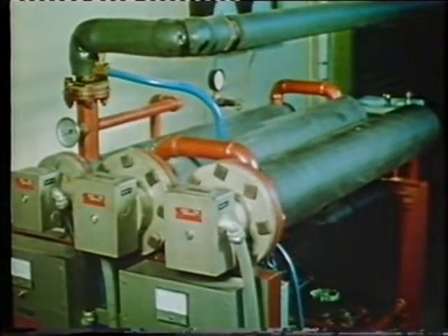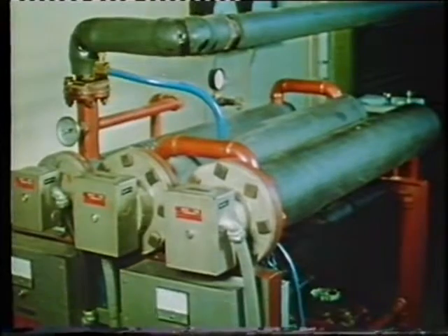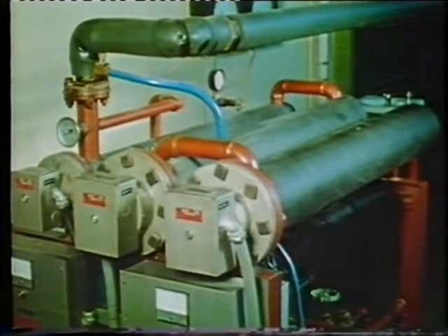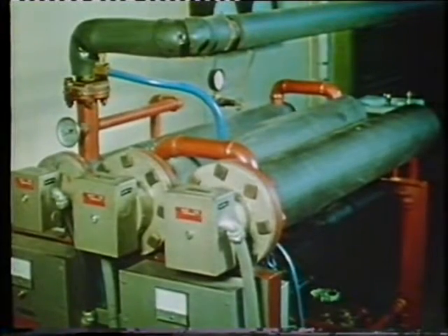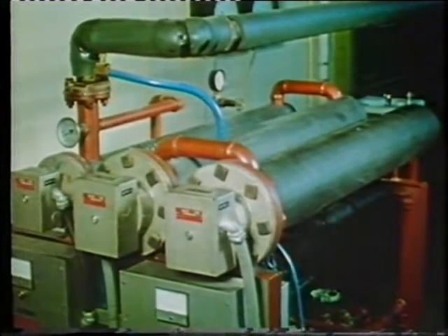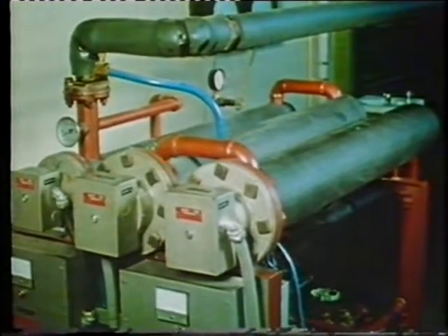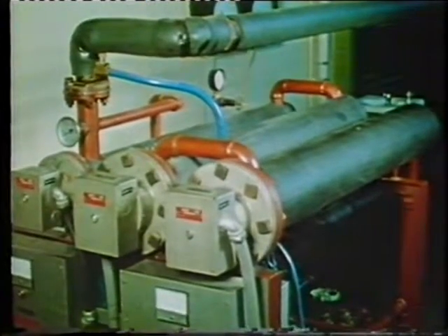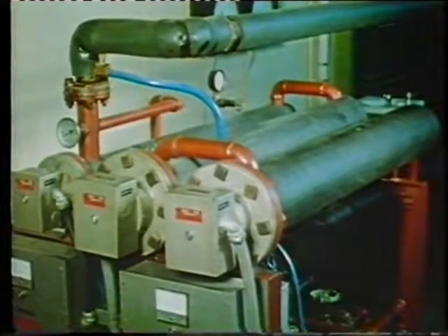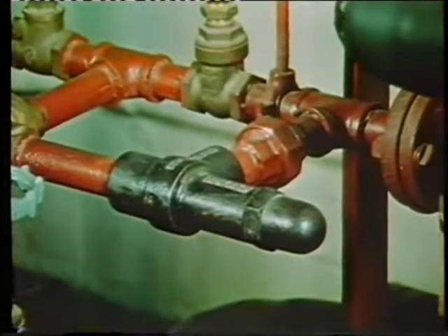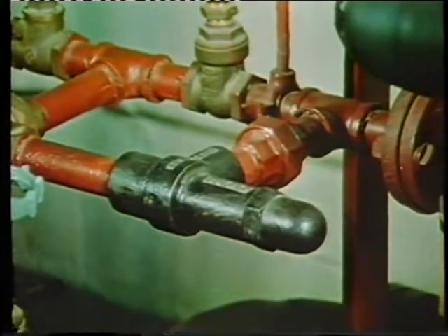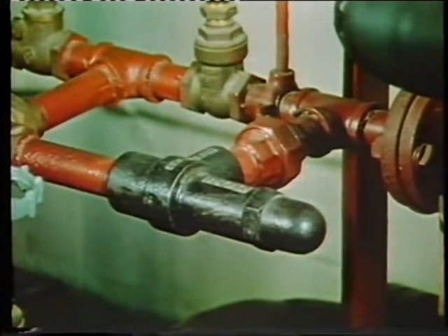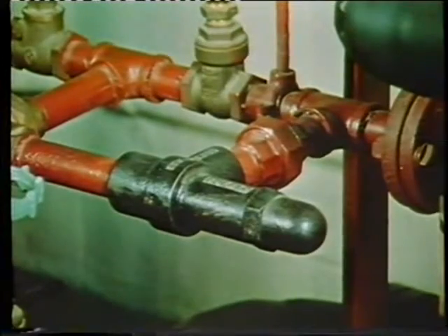Heavy fuel oil ignites easier when it is heated. Steam or electric heaters may be used both at the burner and in the storage tank. Be sure that oil is never heated to the flash point in the storage tank, but is kept between 100 and 120 degrees Fahrenheit for best results. Pressure relief valves at the oil inlet and at the boiler are employed to maintain a set pressure and to bypass excess fuel back to the storage tank.